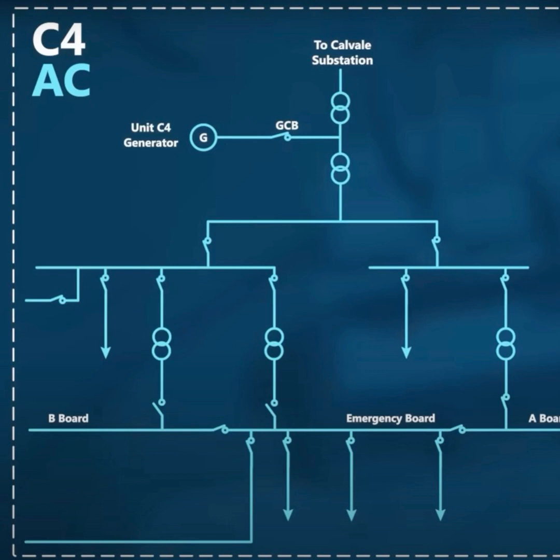But in this case, the ACS was connected to its preferred unit C4 AC bus, and when the unit C4 AC main bus went dead and the station bus still had power, it still did not switch over when it should have. In the investigation, it was found that the ACS automatic changeover component had been damaged in an incident where both Callide unit C3 and C4 simultaneously tripped at 10:57 a.m. on the 13th of January 2021, some 4 months earlier.